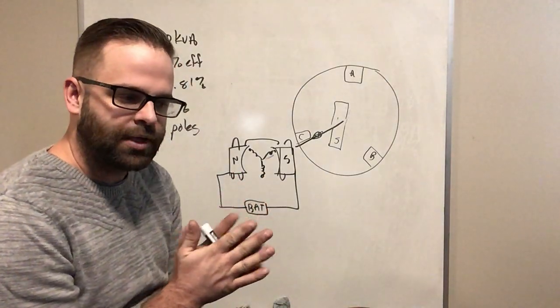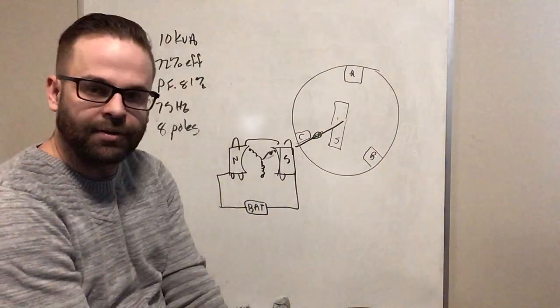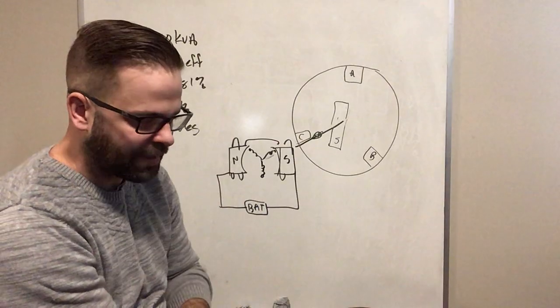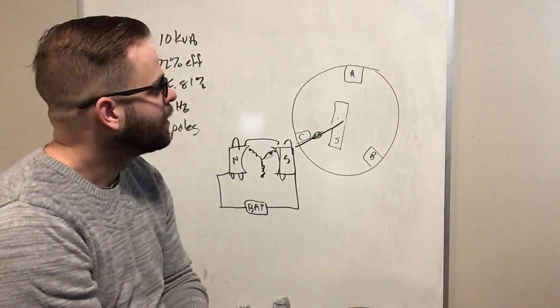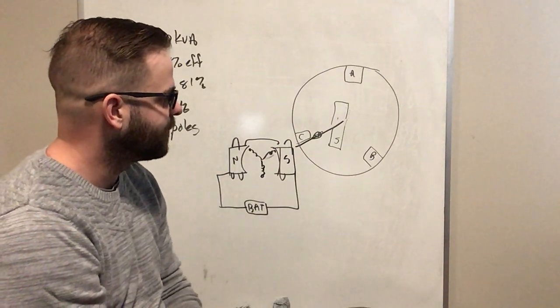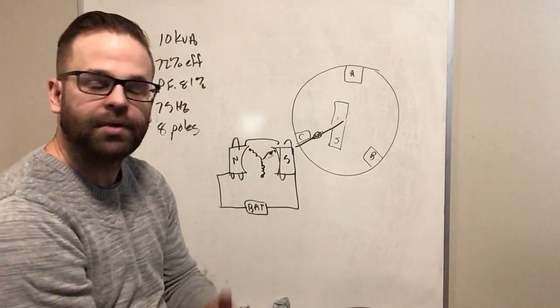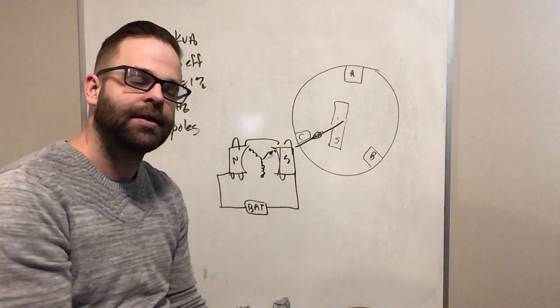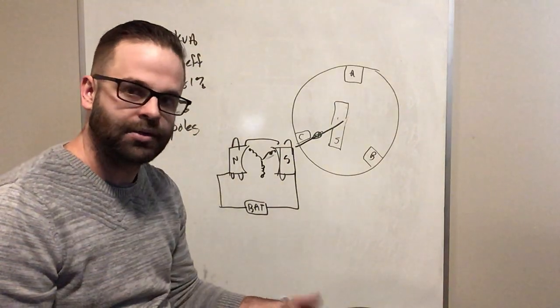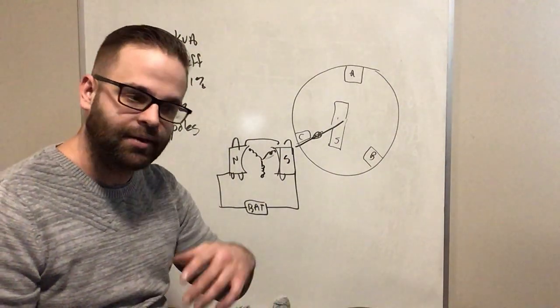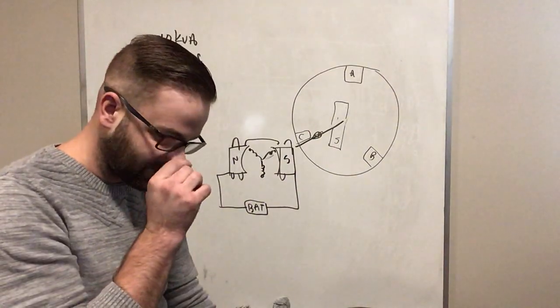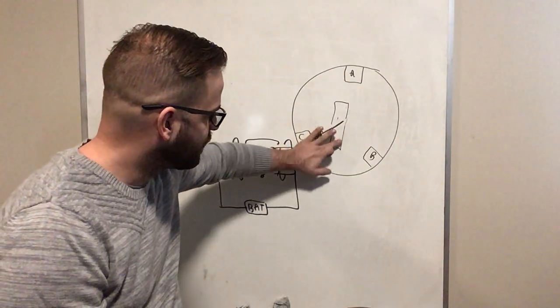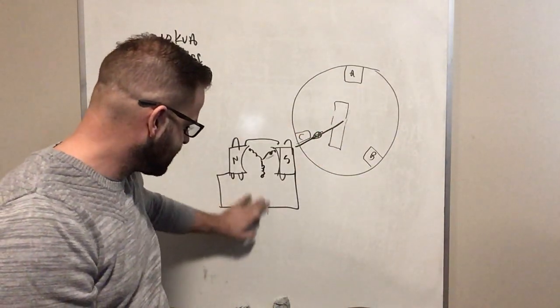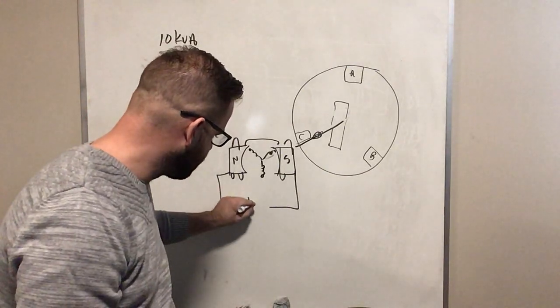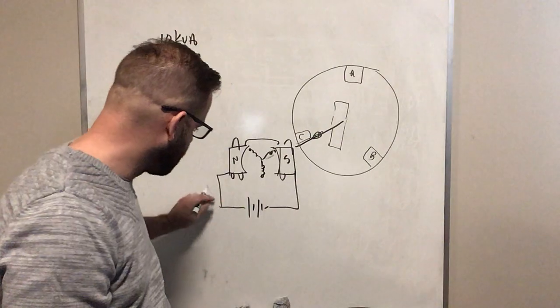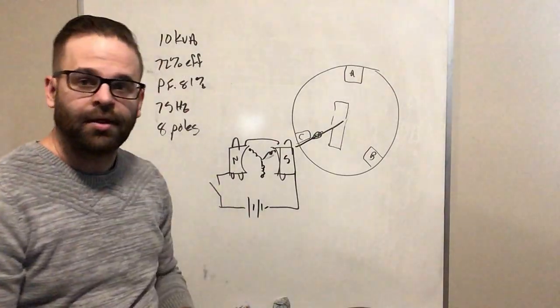But when we go to turn on a three-phase synchronous motor, there are a few things we have to keep in mind. With a three-phase motor, when we go to start it up, how do we establish a rotating magnetic field? Rather than spinning a magnet in coils, now we energize coils, and those coils create rotation on the shaft of the motor. So before we start it up, I'll draw that as a battery, and I'm going to open up the switch. This is the switch to turn on our DC excitation.